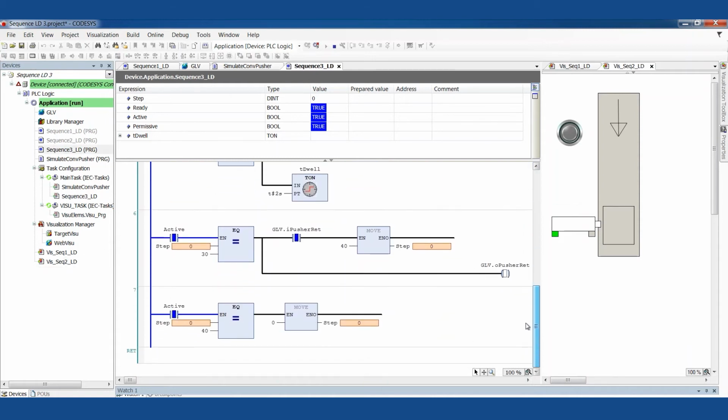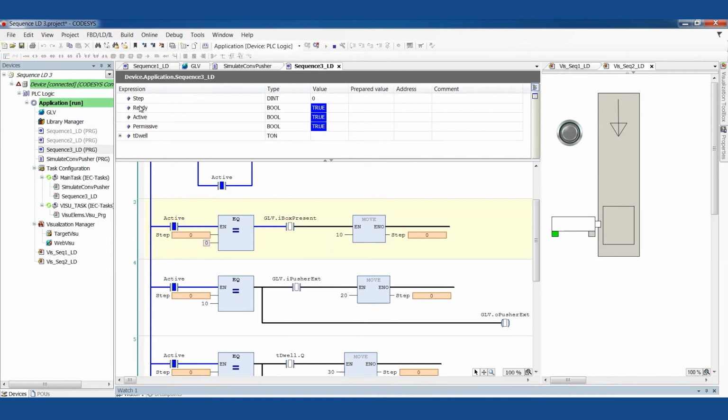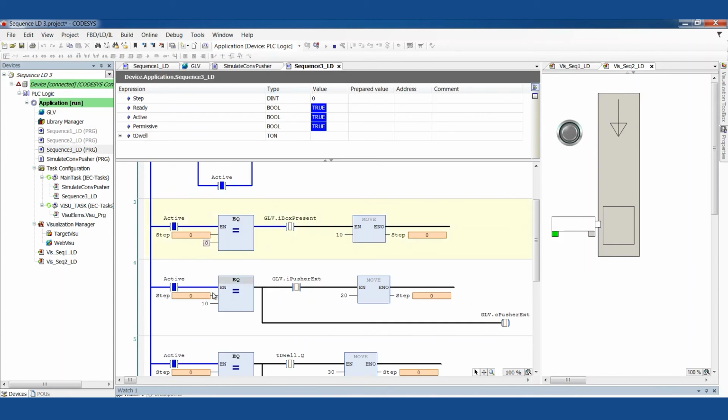This is one of the things I like about this structure. I've already talked about how I can count up by 10, so there's a lot of room in between every step. I also like that there can be a bajillion steps. I've never even come close to running out of steps and had to create another tag like I would have to with the setting bits method. And it's also visible everywhere. I know exactly what step the sequence is in anywhere here because it's everywhere in the code.